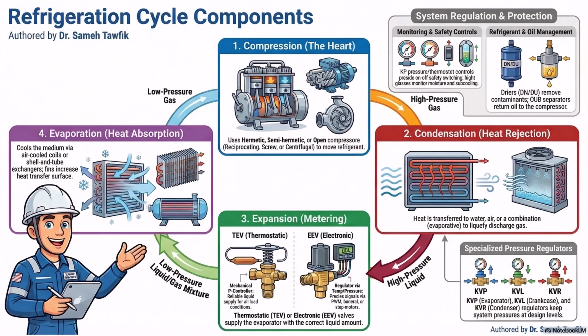And that's bad. Very bad. If you're chilling water, for example, that water might suddenly freeze solid inside the pipes, expanding and bursting the metal. Oh, wow. So the KVP senses that pressure drop and physically chokes the line to keep the pressure and the temperature safely elevated. So it stops the chiller from freezing itself to death.